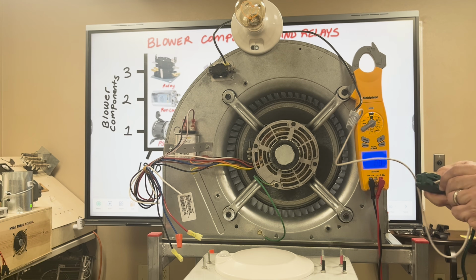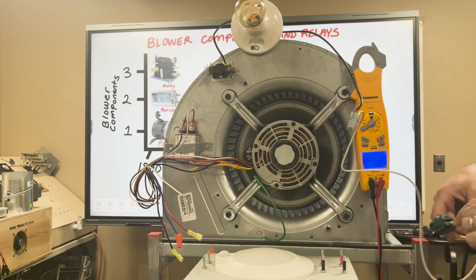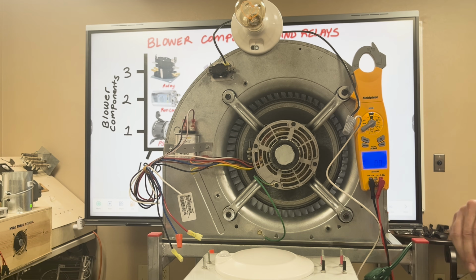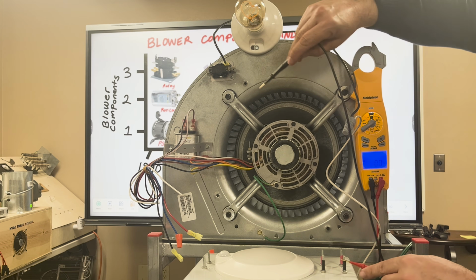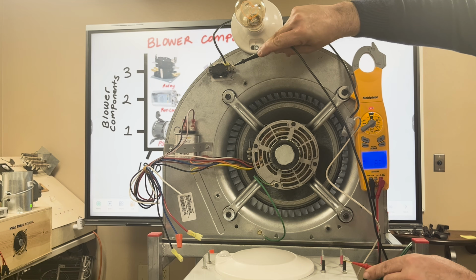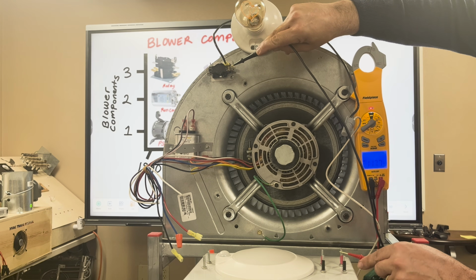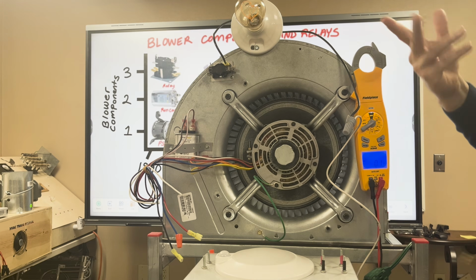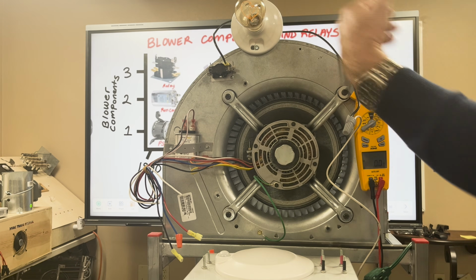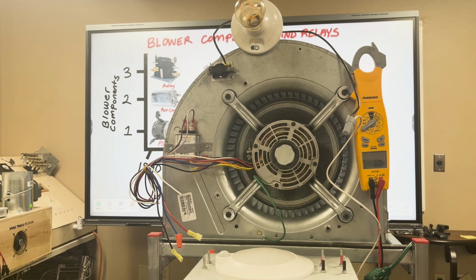So I'm going to plug this back in. I'm going to check my path. Now I have neutral again, and the same thing—we have both legs of power present. I'm reading neutral as if it was a leg of power, because through the bulb, through this filament, I'm getting neutral. That's how that works.